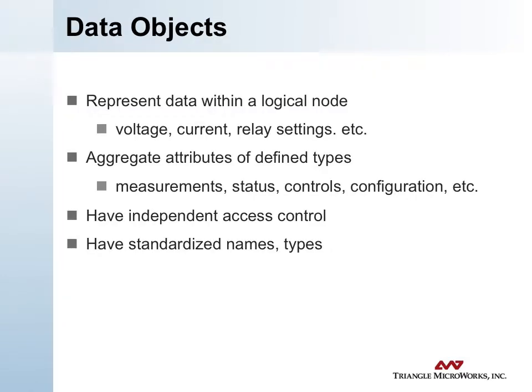Data objects within 61850 represent the real data you're after within the logical node. Examples include voltage measurements, current relay settings, and various controls. They typically aggregate attributes of different types, so they're structures — for instance, the WYE class containing a set of measurements for each of the different phase measurements. They typically have independent access control, and there is standardized naming and typing for all of them.